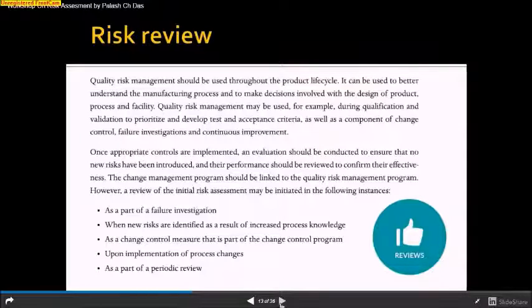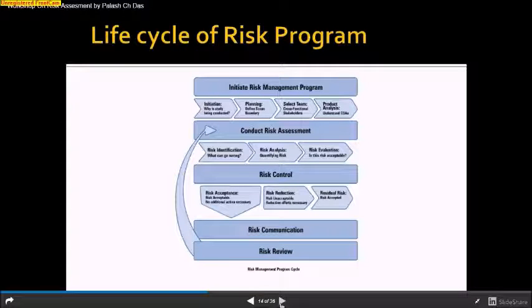Whenever we take a change control and make a critical change, we change something in the process or in equipment, that is also incorporated in your risk management. Upon implementation of a process change, and as part of periodic review, even if nothing has been done in my process, I will again take that risk and review it with my system, to see whether anything new has been added and whether my control measures are weak. We need to give more strong justification and more strong control in my system.